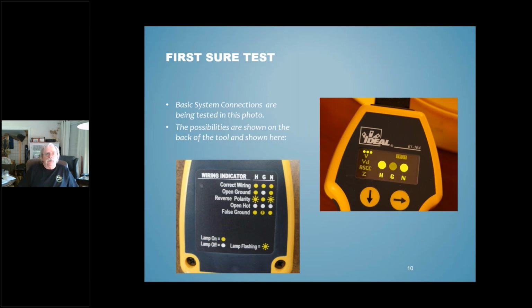I get a lot of questions about a false ground. What is that all about? And a false ground is a neutral to ground link on board the boat. So you need to be cognizant of that. The instructions that come with the SureTest will tell you that it can measure or detect a false ground within 15 feet of the device, assuming a straight wire run.